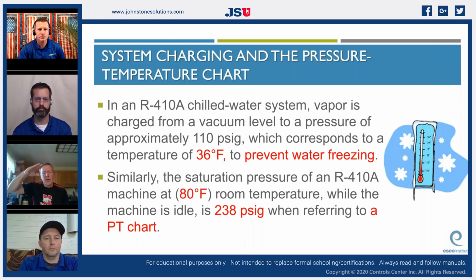So we always correspond the pressure to temperature, and pressure temperature charts are a good thing to be able to read, and I think we should be able to read them by now because we went through them several times. Another example on the bottom here is knowing the relevance of the refrigerant you're working on to the temperature it's in. Once it's in a stable condition and there's any liquid at all, the pressure should match the temperature surrounding it, or the ambient temperature.